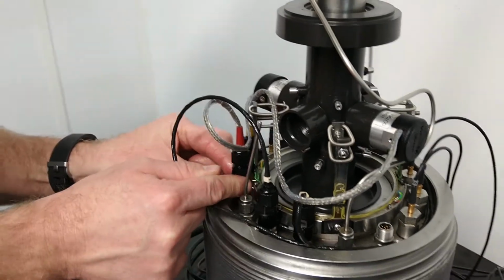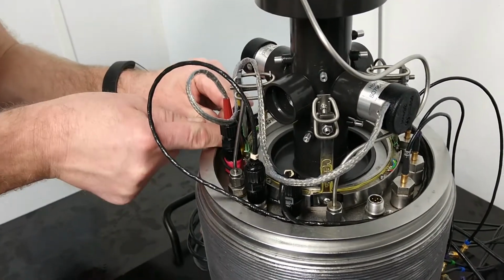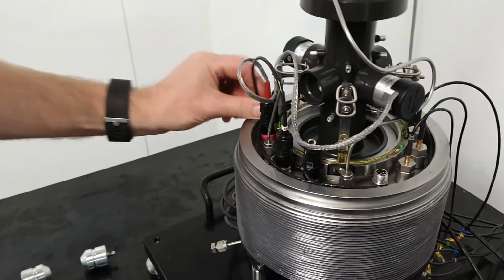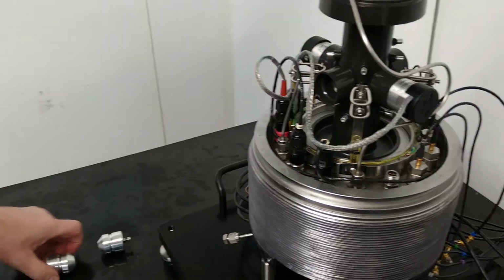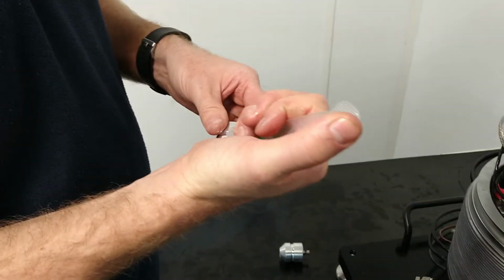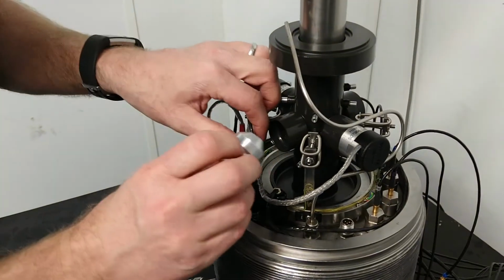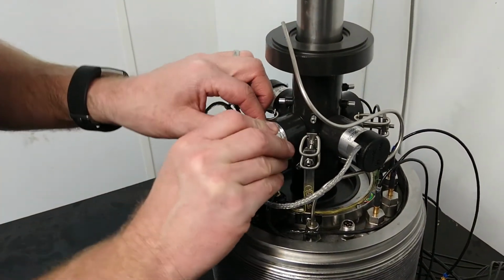The membrane provided is suitable for up to 2 pairs of horizontal acoustic velocity transducers. Any unused locations on the membrane will need to be sealed prior to fitting the cell wall. This can be done by applying grease to the sealing face of the blanking plugs provided.